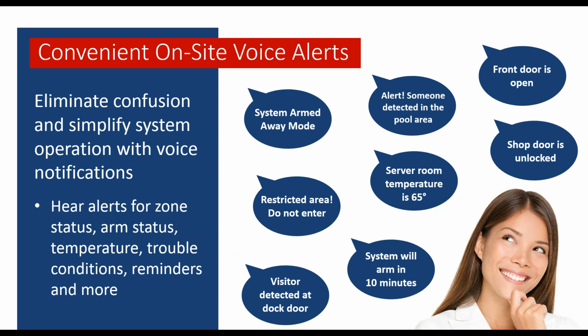You can set the system up to annunciate, say for instance, non-alarm zones. Maybe it's a door or a gate or something leading into a restricted area. Not really necessary to have it cause an alarm condition, but certainly you want to be notified when that zone opens. You can assign those zones as a definition 16 for non-alarm and then assign a voice description to them.